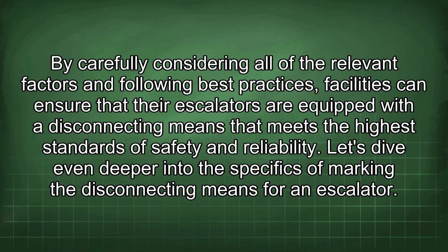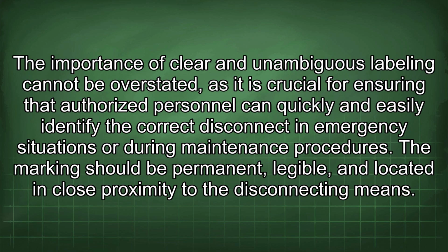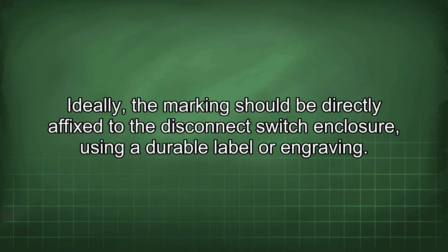Let's dive even deeper into the specifics of marking the disconnecting means for an escalator. The importance of clear and unambiguous labeling cannot be overstated, as it is crucial for ensuring that authorized personnel can quickly and easily identify the correct disconnect in emergency situations or during maintenance procedures. The marking should be permanent, legible, and located in close proximity to the disconnecting means. Ideally, the marking should be directly affixed to the disconnect switch enclosure, using a durable label or engraving.